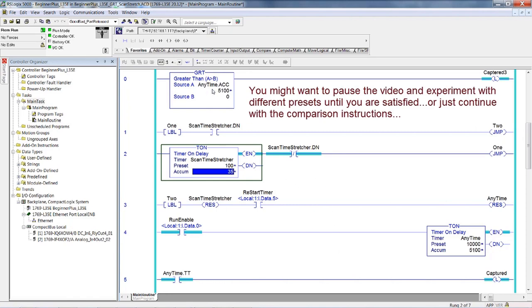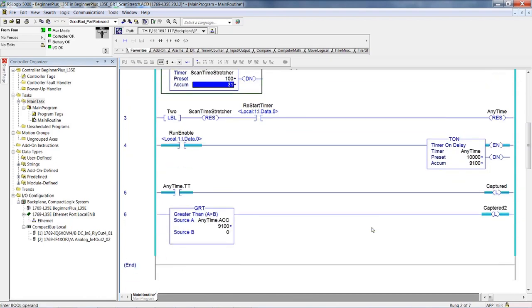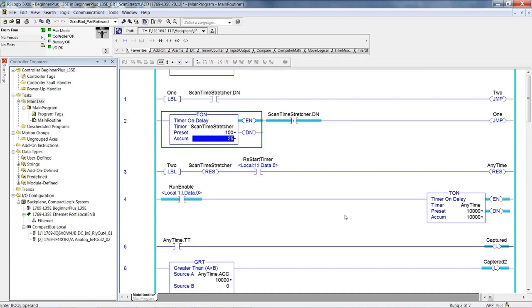We got into all this because we were using the greater-than instruction to analyze our code. There's another thing going on you can't see: the program is not synchronous with the IO update, and you're looking at a screen with a refresh rate that is totally unsynchronous with the controller. So there are a lot of things going on here that are misleading. We had to save the project and go offline. We'll see you next time.